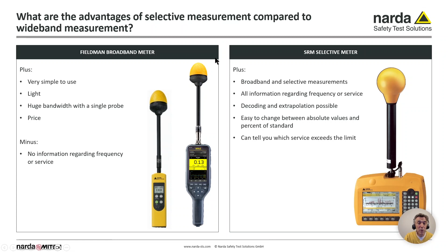You can do it a little bit with shaped probes. This can help already a lot. But shaped probes also don't give you an indication of the frequency. Okay, but it can help you make a judgment. The selective meter can do both. It can do broadband and selective measurement. All information is available regarding frequency or service. It can even do decoding and extrapolation. So it's a more intelligent instrument to do such kind of measurement, but many times it's also not necessary. Many times you measure very low values, then a broadband meter can be already enough.